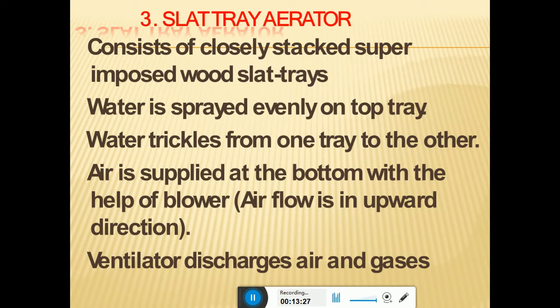This type of aerator consists of closely stacked, superimposed wooden slat trays. Here water is sprayed evenly on top of the tray. The water trickles down from one tray to another, and air is supplied at the bottom with the help of blowers. Because of that, the aeration takes place, and the ventilator discharges the air and gases.